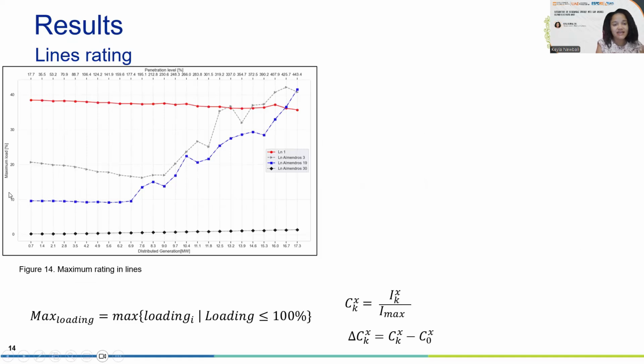In this image, we can see feeders rating. Here is the maximum rating registered for some feeders in the circuit in each penetration level. For the lines at the beginning of the circuit, the rating goes down with the penetration of renewable energy. The lines in the middle of the circuit are the ones that have more variation in the rating, with a rising rating. And the lines at the end of the circuit have very little variation in the rating. We can see that the lines have spare capacity to hold distributed generation. So lines rating doesn't have a hosting capacity either.